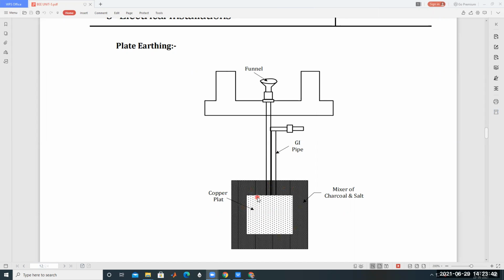But in pipe earthing, there are layers: first charcoal, salt, charcoal, then salt, charcoal, salt. Like this, charcoal and salt layers are formed in the pipe. But here, this mixture of charcoal and salts is used in plate earthing. So this copper plate is buried into the ground and welded to the GI pipe, the galvanized pipe, and also here there is a funnel arrangement.